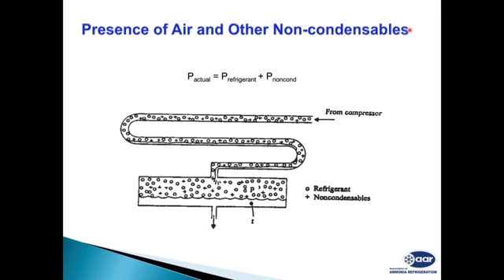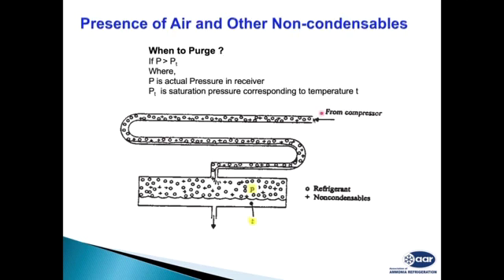So how do we know whether our system has non-condensable gases or air in it? I'm going to say air now, because the percentage of air is much more than the other non-condensable gases. But what I am going to say is how we know whether there is air in our plant or not. We can always measure, we know our compressor discharge pressure.